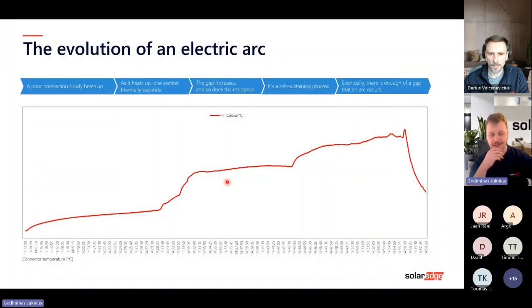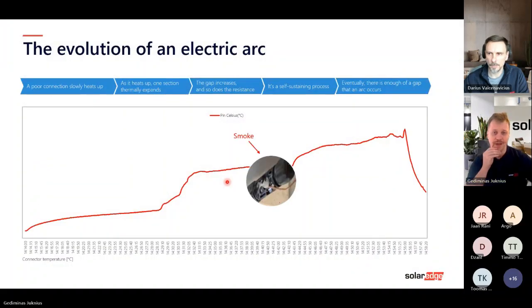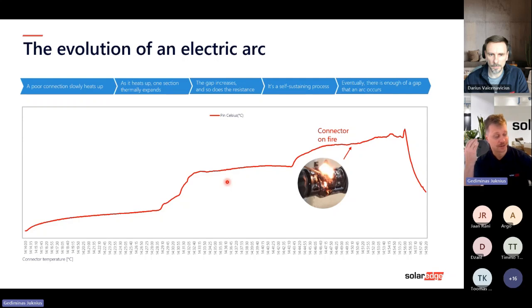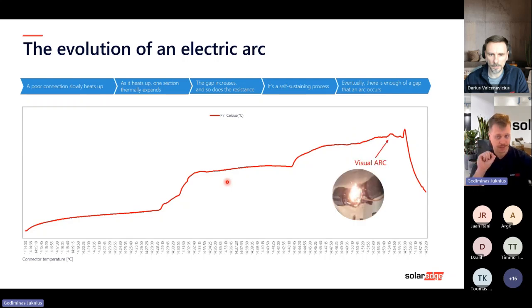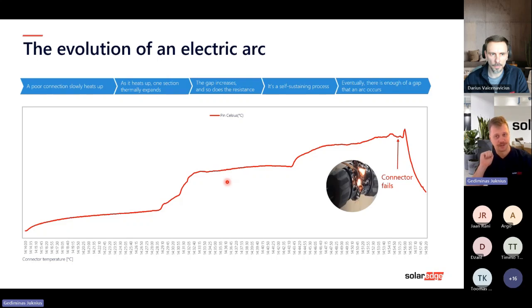So how does it look in theory? We did a really nice study, and we see once there is a problem in the MC4 connector, there is a small smoke which comes from the connector. Then you see the fire on the connector. Then there is a visual arc. At this moment, the inverter, if it's equipped with the AFCI, should notice that, oh, we have an arc, we have a problem on the roof. It should stop production, shut down the current flowing. It should stop everything for safety reasons. If the inverter is not equipped with AFCI, what happens? It burns until the gap between the connectors is too big to contain the current flowing. So as long as the distance is okay, you will see the constant arc happening.